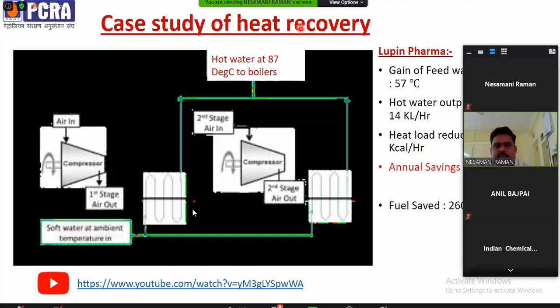This is one case study to support the technology. The company is Lupin Pharma. What they did is, they have a two-stage compressor and they have implemented this heat recovery system. After the first stage, the soft water at ambient temperature goes through a heat exchanger and extracts the heat. Then it goes to the second stage exit and again extracts the heat. Through a common header, both the stage waters combine and go to the boiler as feed water.